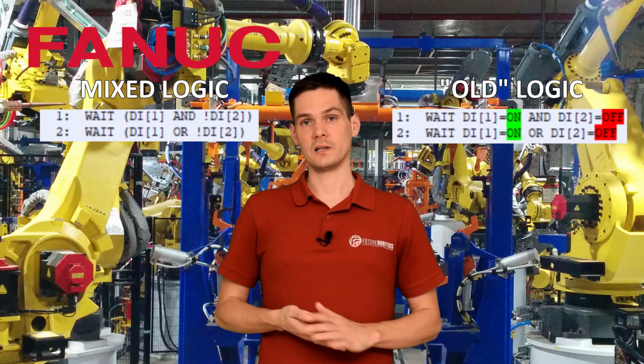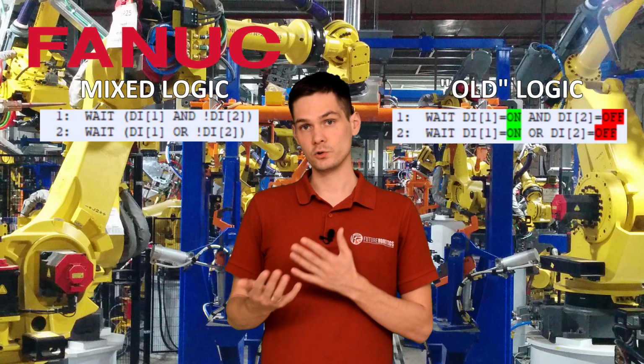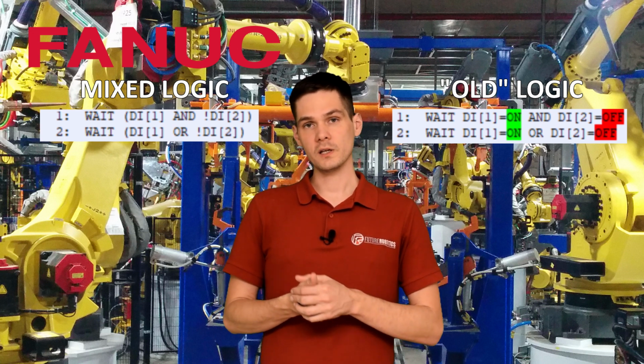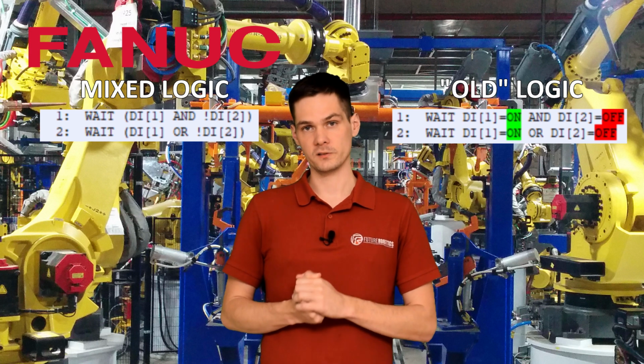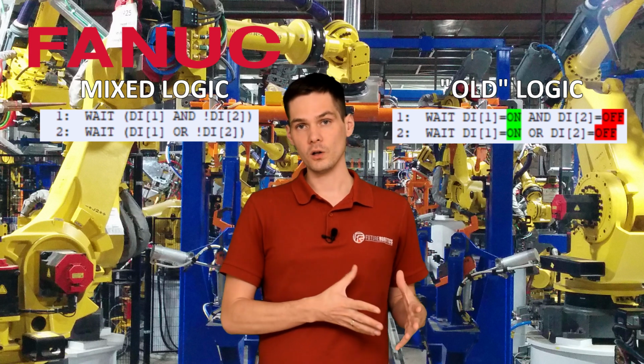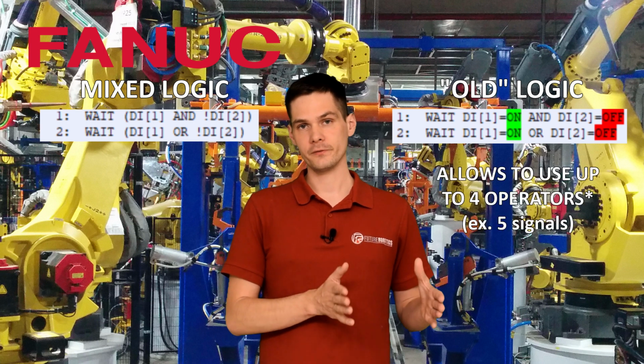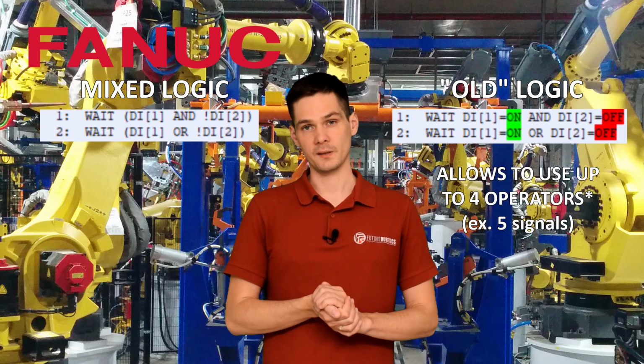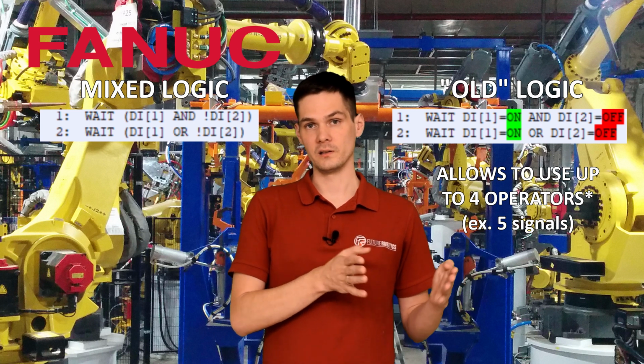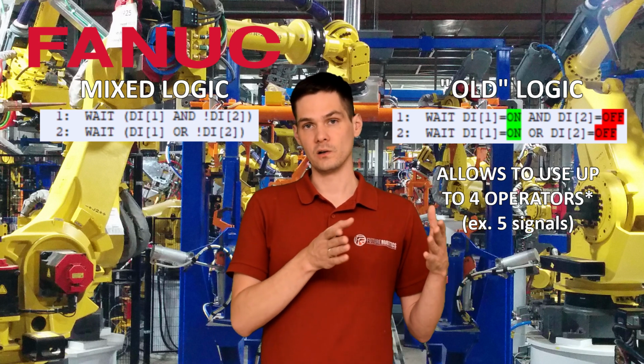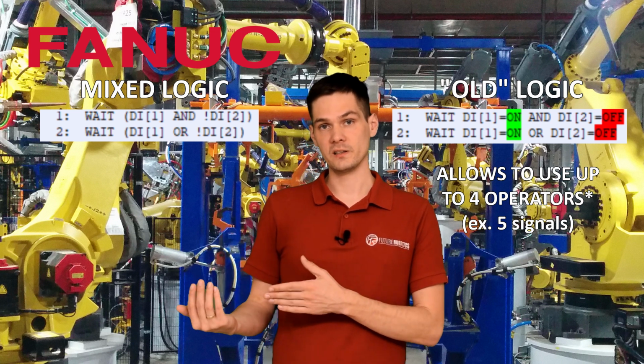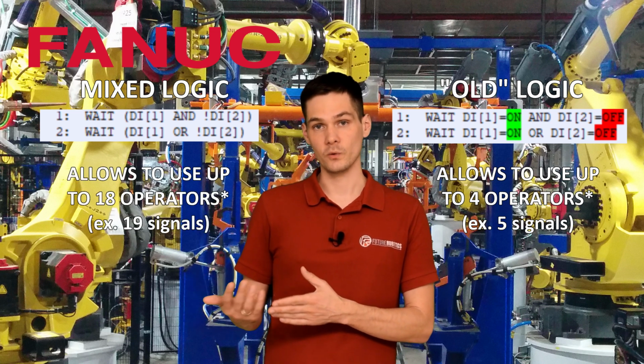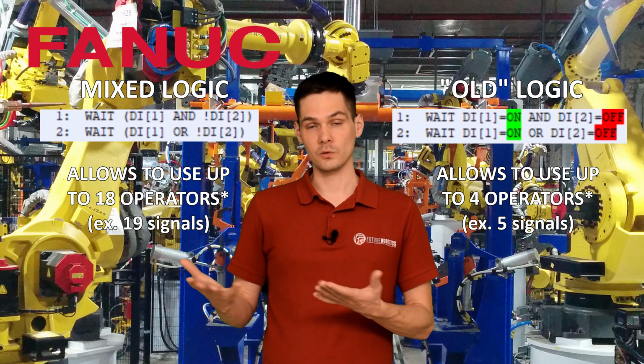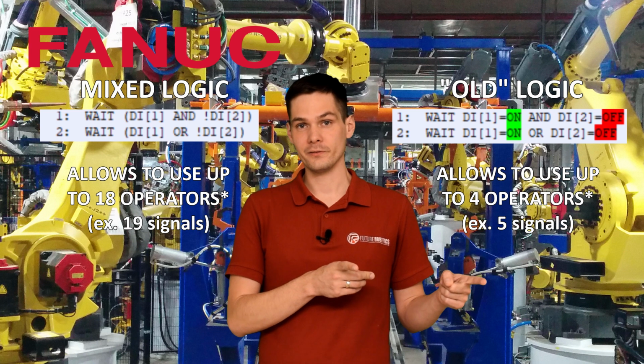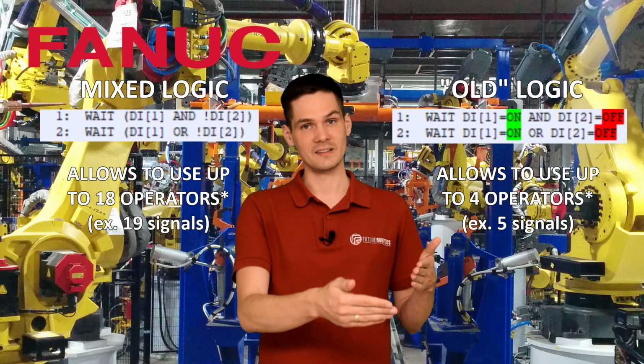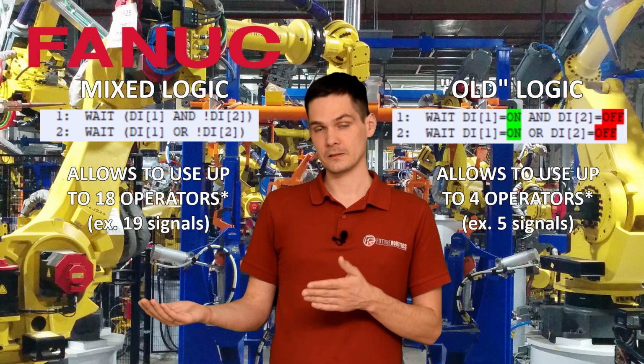So let's talk about the differences and why you should use the mixed logic. So first of all, you can use many more operators while using the mixed logic. In the old logic, you can only use up to 5 conditions for a statement. For example, for an if statement, you can only put 5 conditions in there that the old logic can handle. Where in the mixed logic, you can use up to 19, which I think is a very big difference. So you can imagine an if statement where you have only 5 options, like if DI this and that, where there is a 19 on the other hand. So that's the first thing.